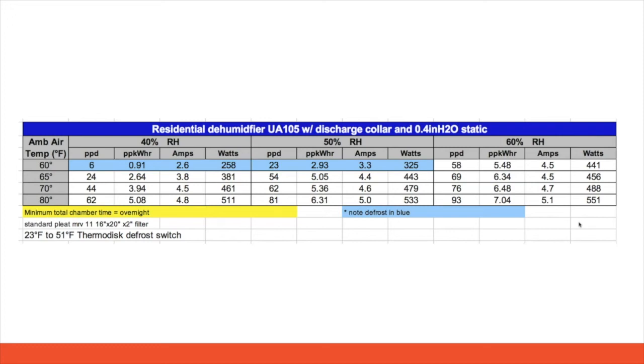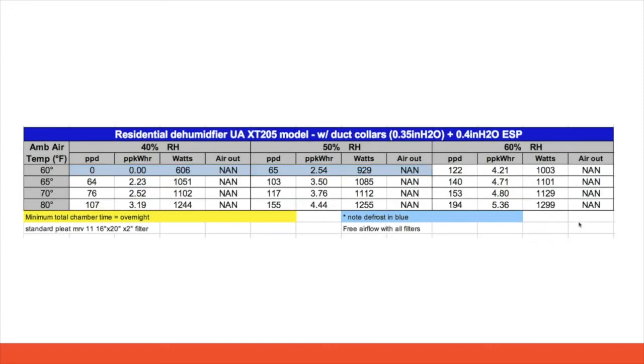So performance data is really important, and something that we are adding to all our dehumidifiers at the new DOE conditions. So very important to know that, again, dehumidifiers were rated in the past at 80, 60 for those pints of water removal, and we need to think about the different conditions we're putting those in and getting those performance curves. And this is for our 205 unit. So again, this is 0.4 water columns, and that 205 at 70 degrees and 60% relative humidity is 153 pints.